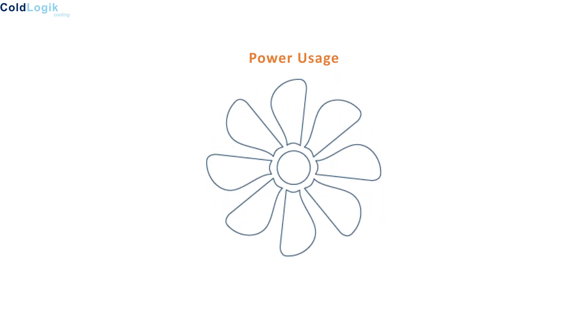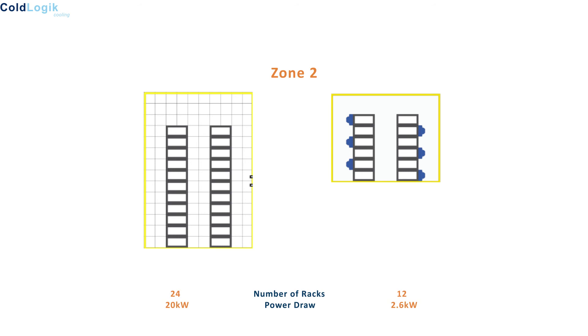In zone 1, we reduced the number of racks from 24 down to 12 and deployed an RDC to every third rack. The power draw to cool the 12 racks with a total load of 72 kW is 1.208 kW. This is down from the original 14 kW used by perimeter cooling technology, representing a drop of 93% in energy used to cool the same space. Similarly in zone 2, we reduced the number of racks from 24 down to 12, but this time deployed a rear door cooler to every second rack to cater for the higher rack kW density. The total ColdLogik power draw to cool the 12 racks with a total load of 120 kW is 2.6 kW, representing a drop of 88% from the original 20 kW used by perimeter room cooling.